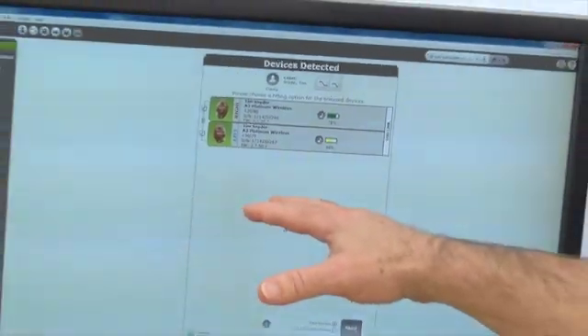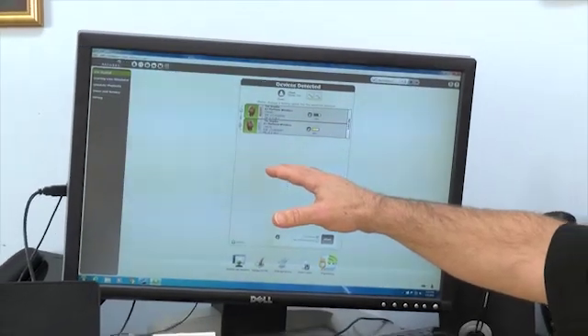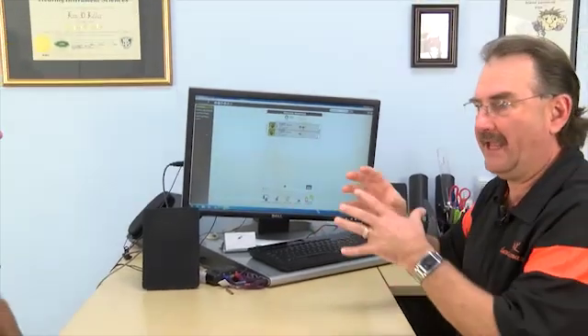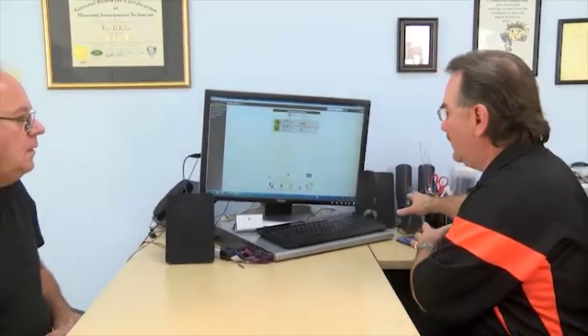Now how did the hearing aids show up on this screen? It's the magic of technology with the hearing aids, because these hearing aids actually have antennas in them and what they'll do is they're wirelessly connecting to the computer. Now what these hearing aids also do is they'll talk to each other and they'll let each other know what's going on on each side of them and they'll self-adjust.